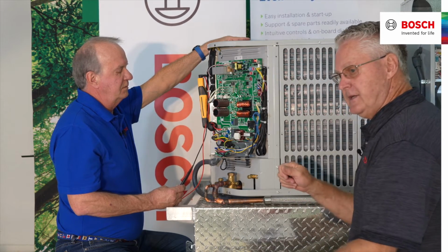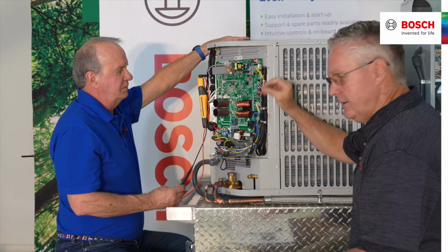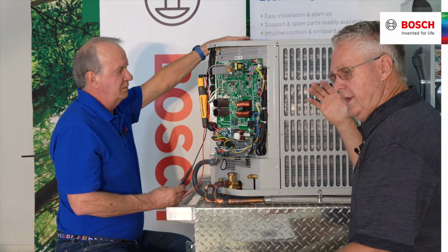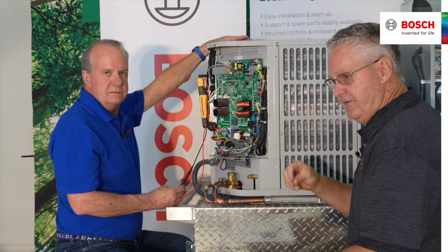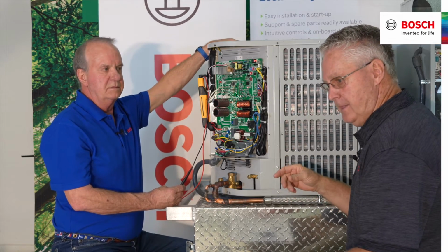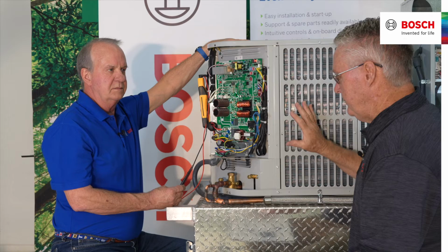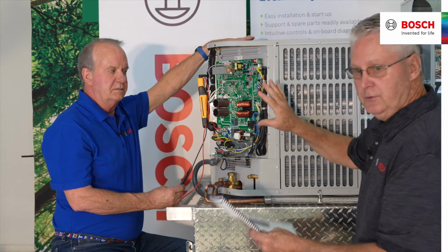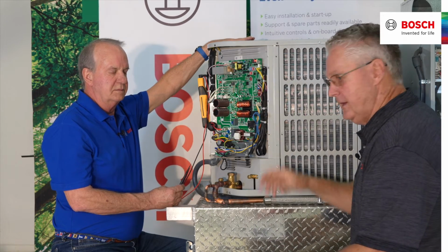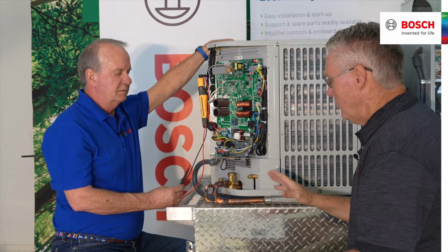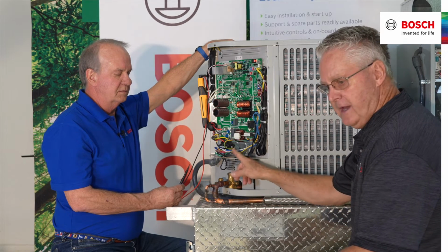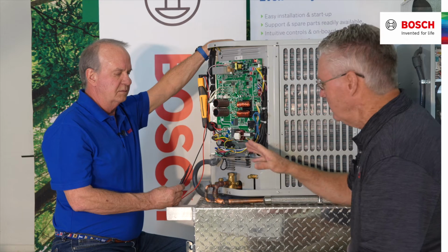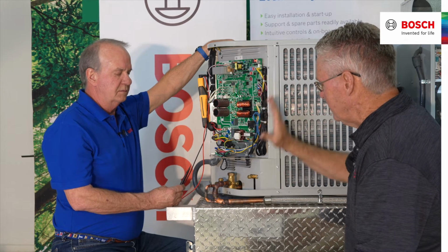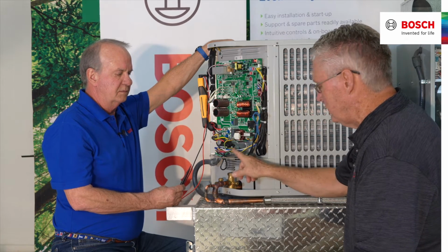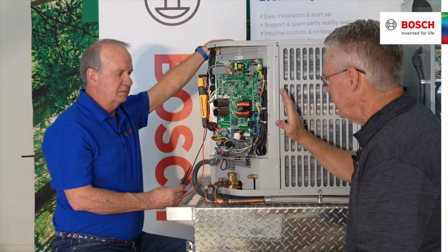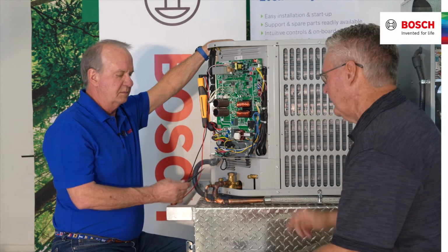Remember that I pulled the disconnect, the screen went black, and we are now in a 5.5 minute time delay that we're going to be susceptible to because of the board's delay. It's not a low voltage board. Remember that we do not have an R coming out here. We don't have a power wire coming out here. We don't energize the board through the 24 volt circuitry. We energize and light up the board through the L1 and L2 circuitry.